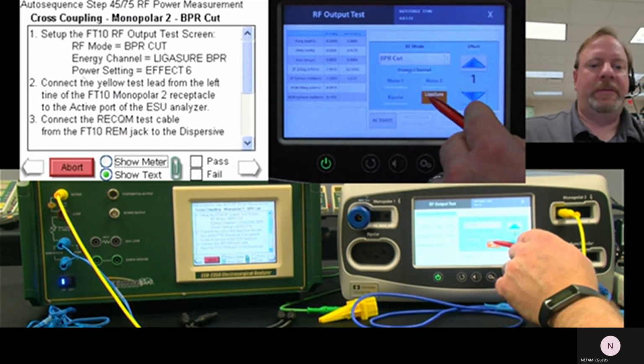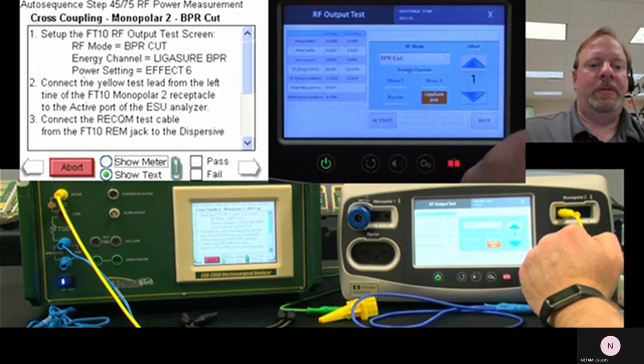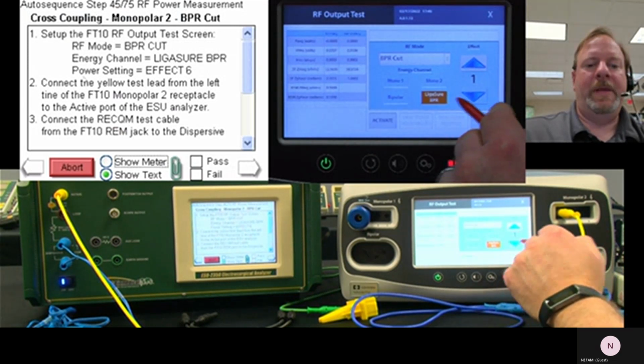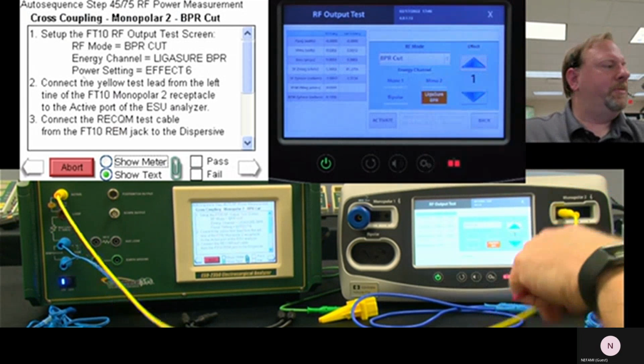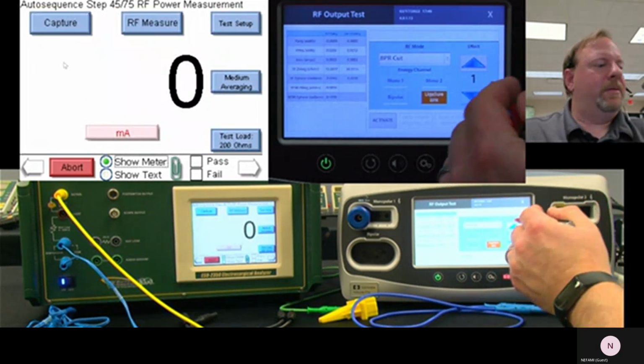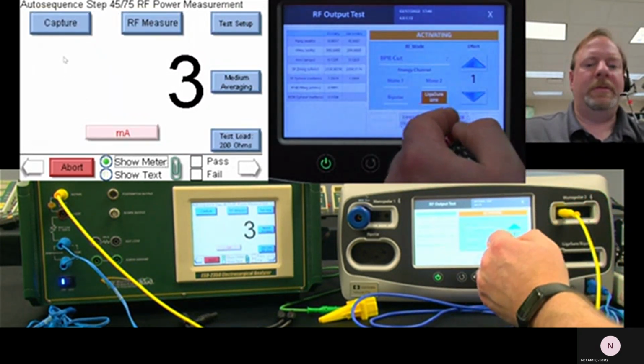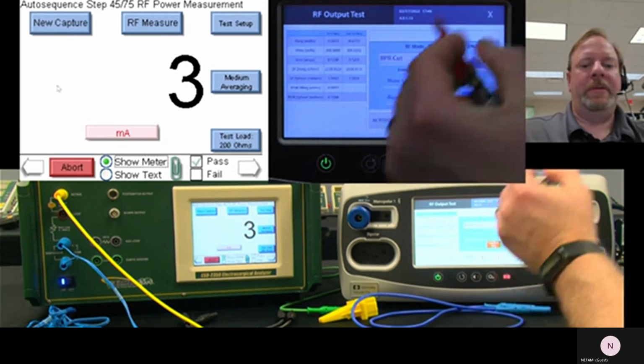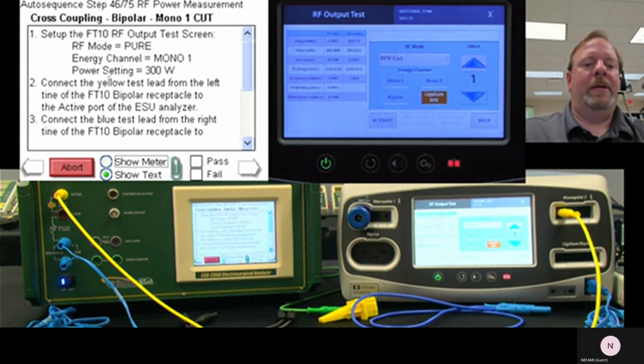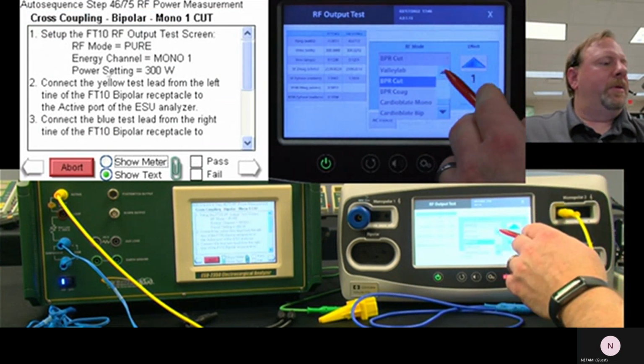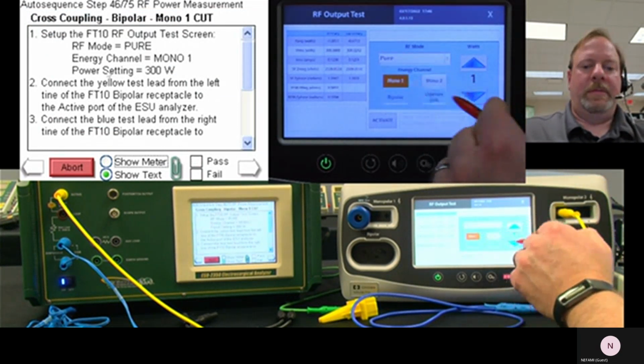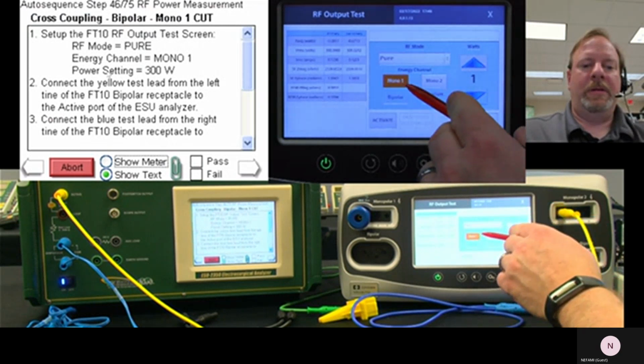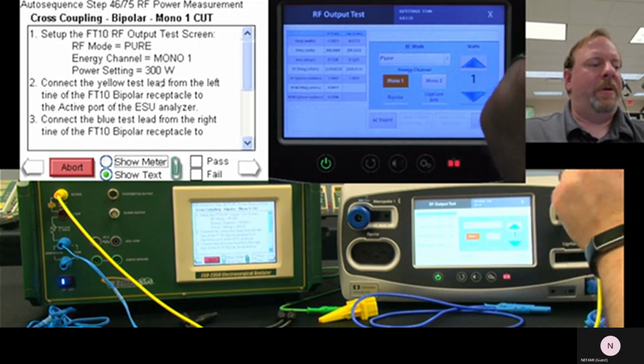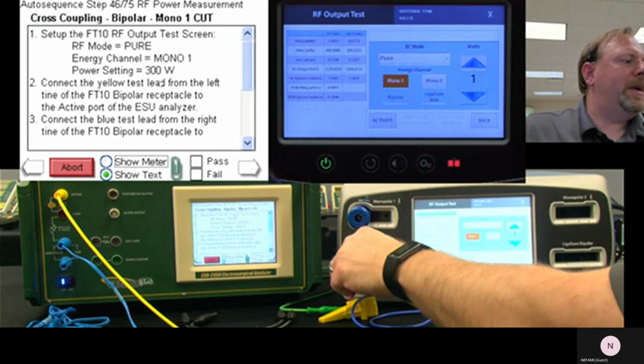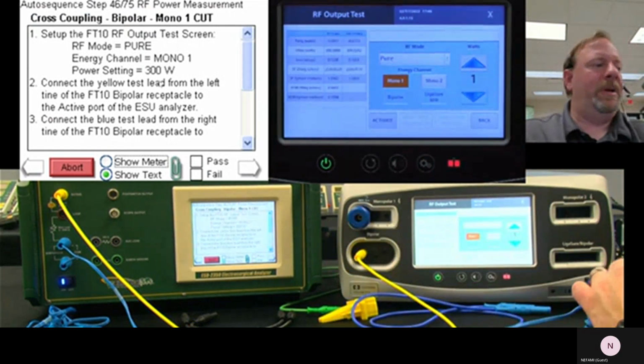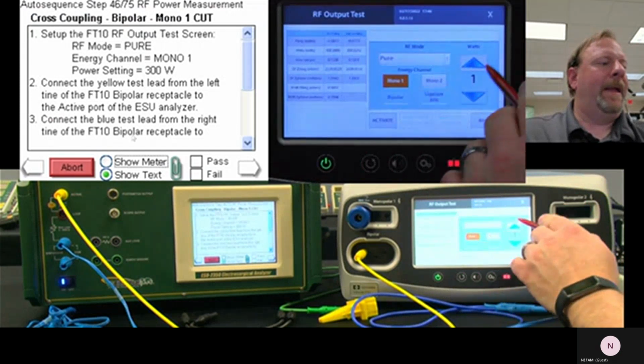BPR cut. LigaSure. Energy channel is LigaSure. Yep. So now we're still connected to monopolar 2. And we do our measurement, activation, capture, deactivate. Go to pure. Energy channel, mono 1. So now we're going to the left hand of bipolar. So now we're going to say how much energy comes out of the bipolar port when monopolar 1 is activated at maximum power.